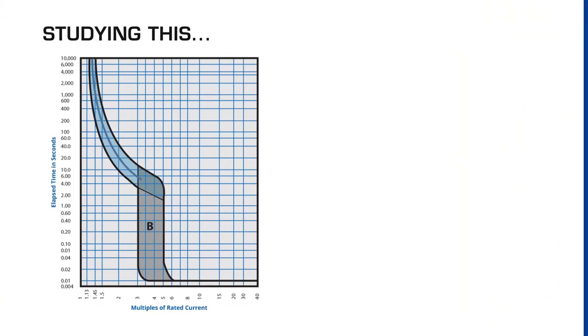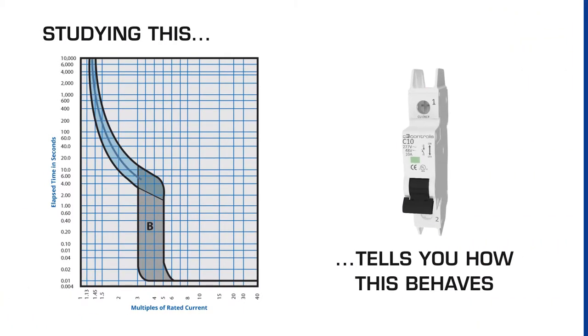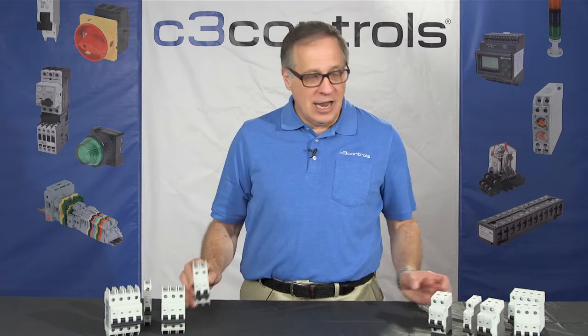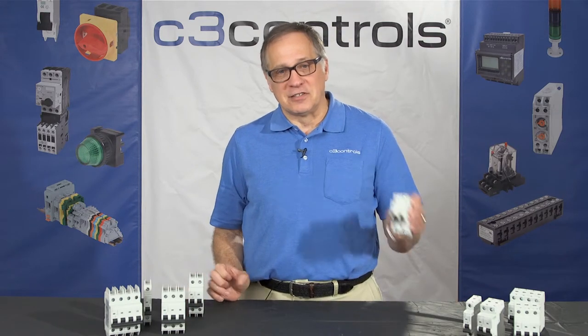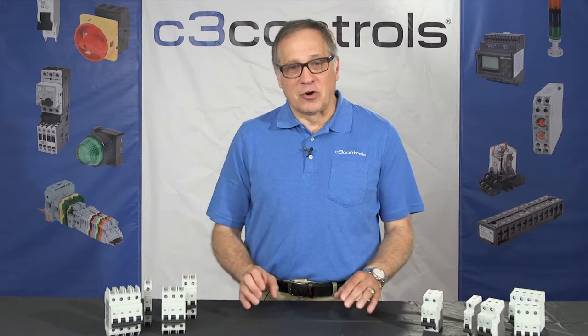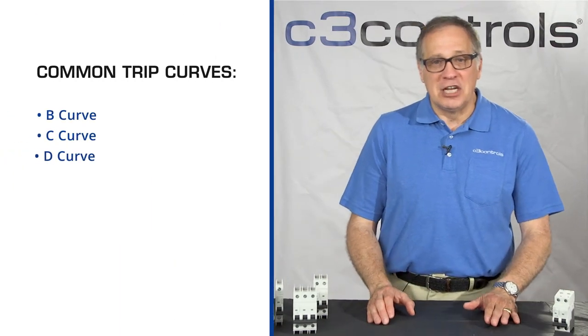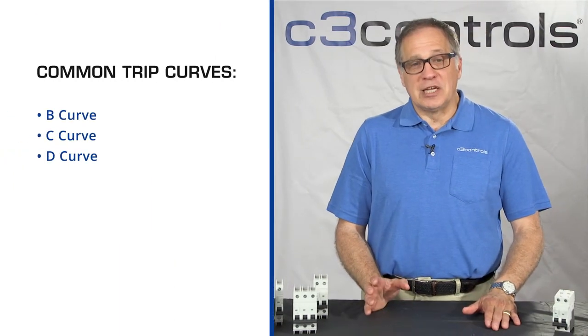Let's dive into the next question: what exactly is a trip curve? Simply put, studying this will tell you how a device behaves. Trip curves are graphs provided by the manufacturer which represent the expected behavior of a circuit protection device. There are many different forms these devices come in. For this video we're referring to UL 489 and UL 1077 devices. The most common trip curves are B curve, C curve, and D curve, all of which C3 carries.